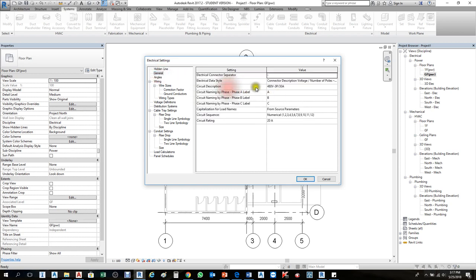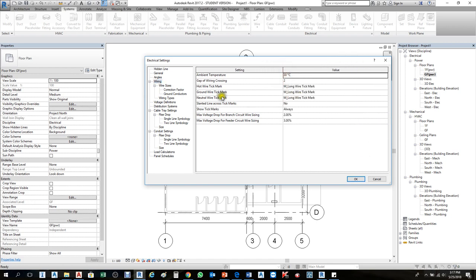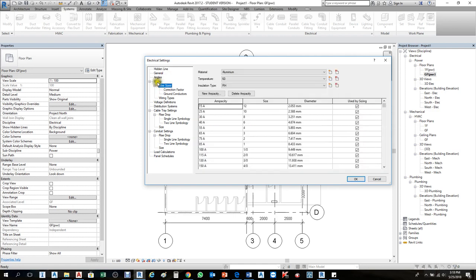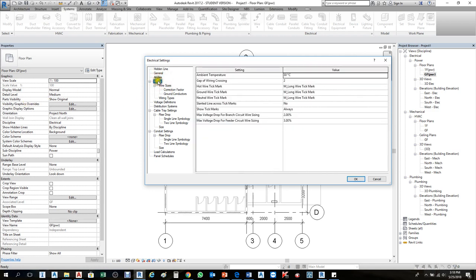Under General, you'll see that circuit description is set by the distribution system listed here. We'll go through settings step by step — from 2016 to 2017 some settings changed but most are typical. Under Wiring, the gap setting controls what happens when one wire passes another wire, creating a 2mm gap. For hot wire, ground wire, and neutral — phase, earth, and neutral — these line markings aren't used in Revit files, only in AutoCAD sometimes. Wire size is more important.